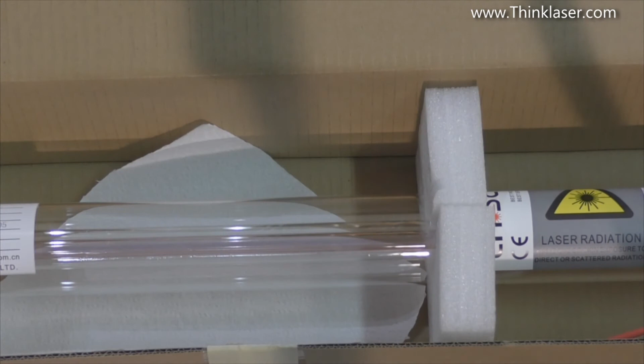The fact that it's pink tells me it's been flash coated on the inside with gold, and that gold flashing is an indicative feature of a long life tube. It helps to recombine any free oxygen with the carbon monoxide to keep the CO2 at a reasonable level. It delays the death of this tube, and so this is a hallmark of a very, very good tube. You won't find that catalytic coating in most economy tubes, should we call them.